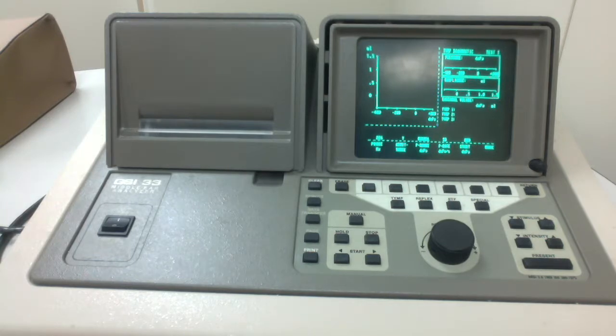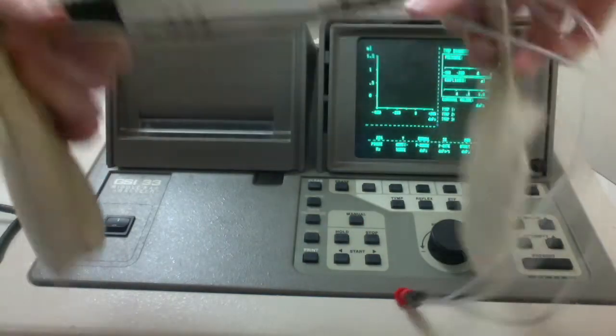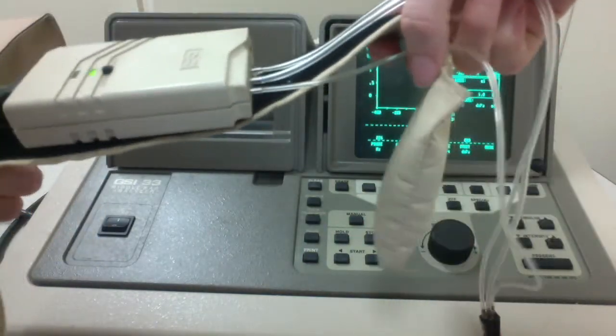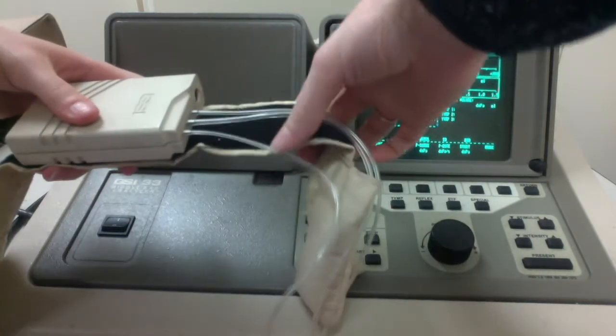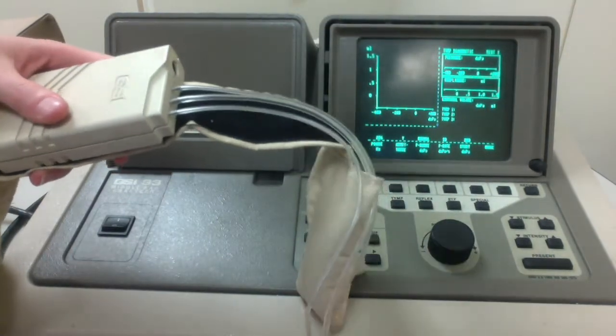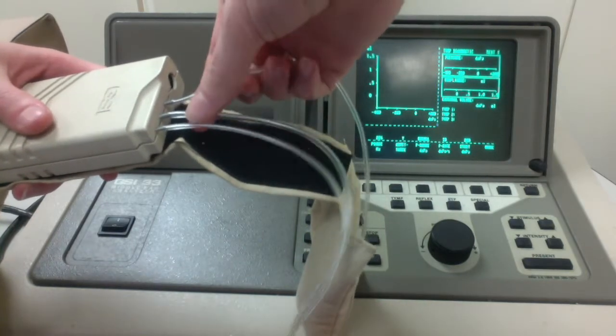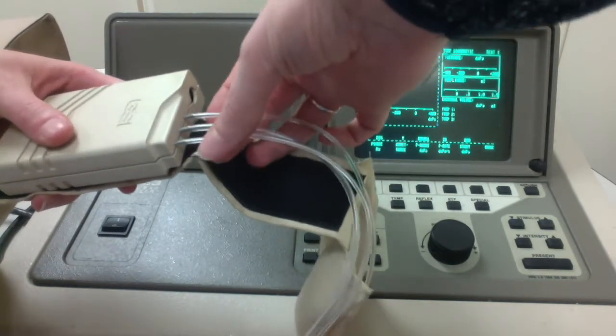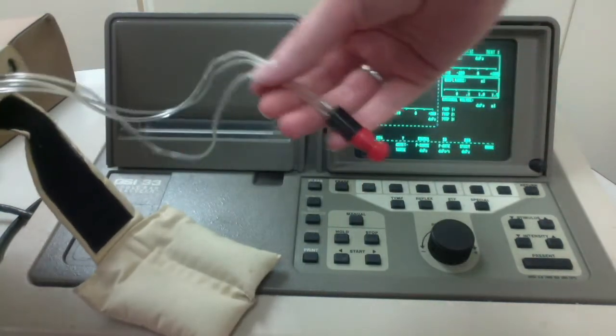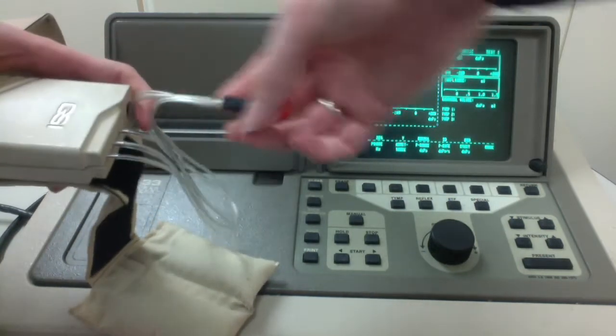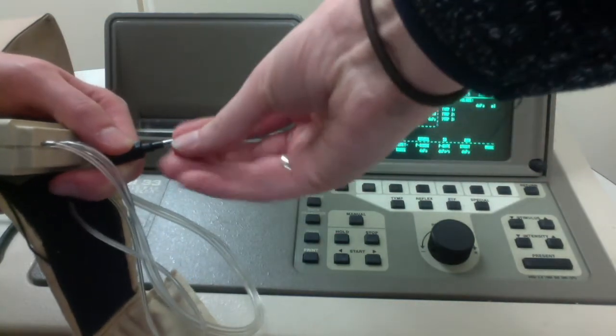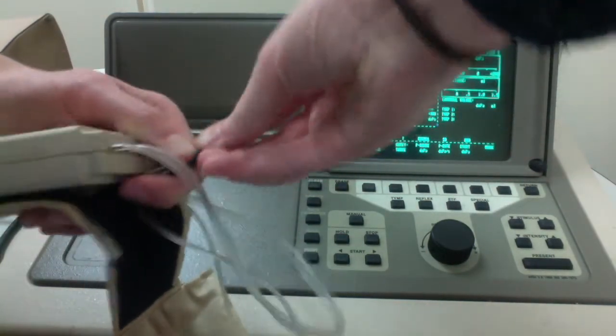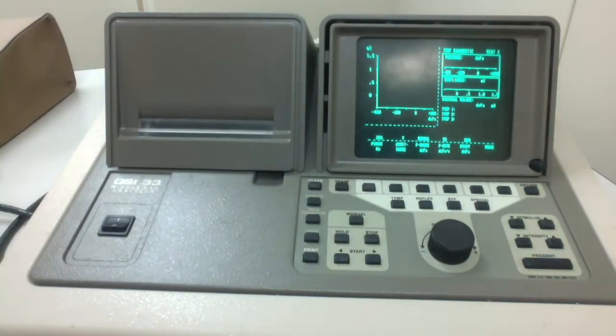So we can start talking about other parts of the equipment. This is our shoulder box there. It has two weights coming off of it that we use to keep it on the shoulder. It has three different tubes coming off of it. One of the tubes is a speaker to produce the different tones. Another is the pressure pump, and then the third would be the microphone, which would detect the middle ear's response. All three tubes go to a single probe tip. So that would be the probe, and then you can put on different tips. We have different colors and different sizes of those. And you just always make sure that when you put it on, it goes all the way down. We don't want anything leaking out.